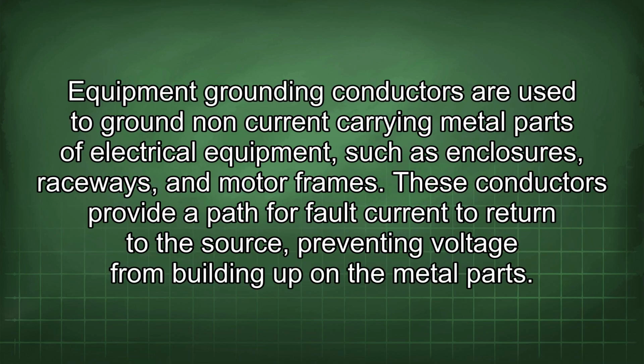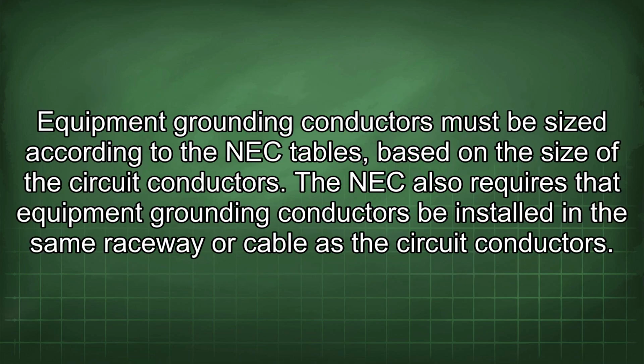Equipment grounding conductors are used to ground non-current carrying metal parts of electrical equipment, such as enclosures, raceways, and motor frames. These conductors provide a path for fault current to return to the source, preventing voltage from building up on the metal parts. Equipment grounding conductors must be sized according to the NEC tables based on the size of the circuit conductors. The NEC also requires that equipment grounding conductors be installed in the same raceway or cable as the circuit conductors.